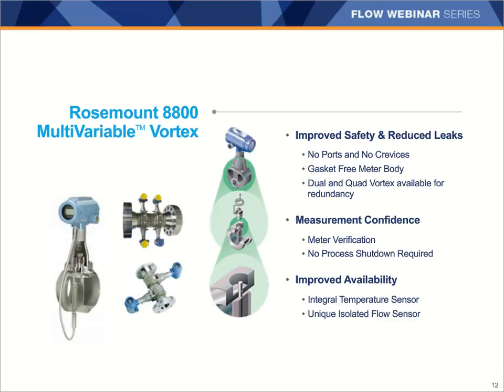One signal can be used for the basic process control system, or BPCS, and the other for the safety instrumented system, or SIS, or both can be used for the SIS to enable redundancy for higher SIL ratings. Rosemount also provides a quad vortex, which enables 2 out of 3 voting schemes for SIS, plus basic process control, or you can use it for 3 out of 4 voting. The quad vortex has 2 meter bodies, primary elements or shedder bars, and it has 4 independent sensors and 4 independent electronics.